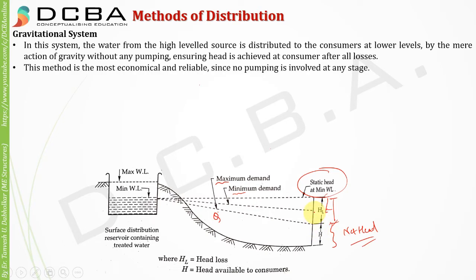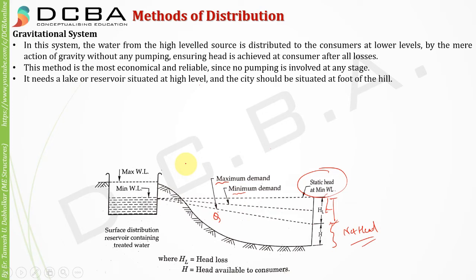This method is the most economical and reliable since no pumping is involved at any stage. During a fire outbreak, the worst thing that can happen if you are depending on a pump is that your pump fails — then you cannot supply water. The gravitation system proves better because it depends on no pumps; it depends on gravity, which is always present. It needs a lake or reservoir situated at high level with the city at the foot of the hill. Pumping is normally not required at any stage.